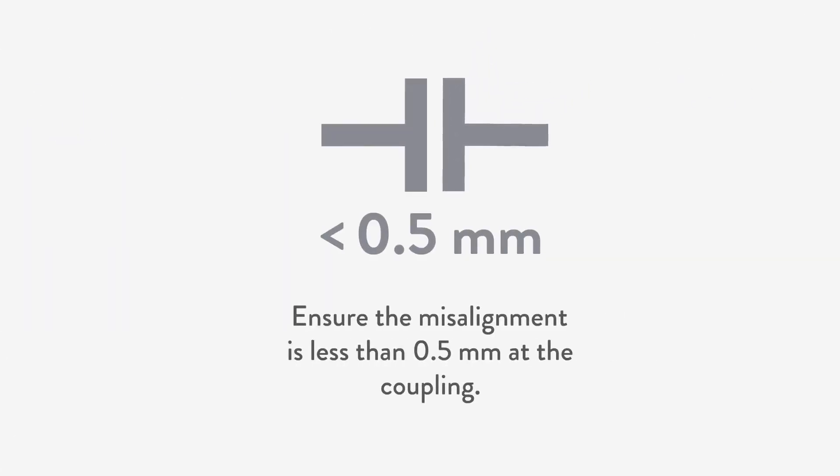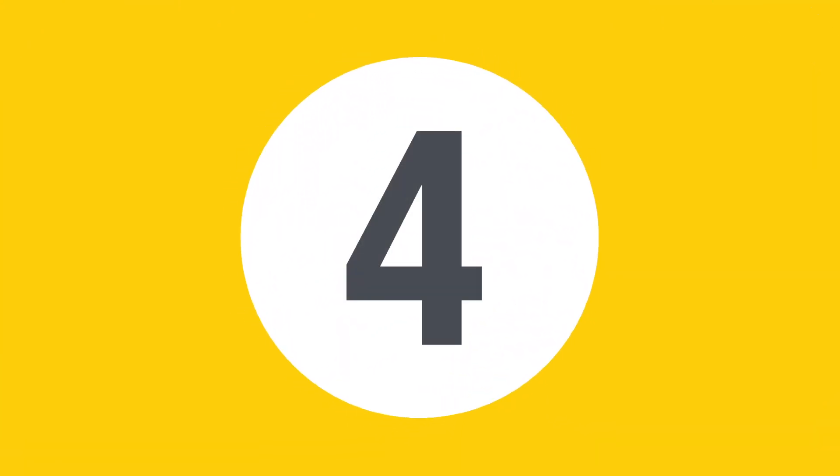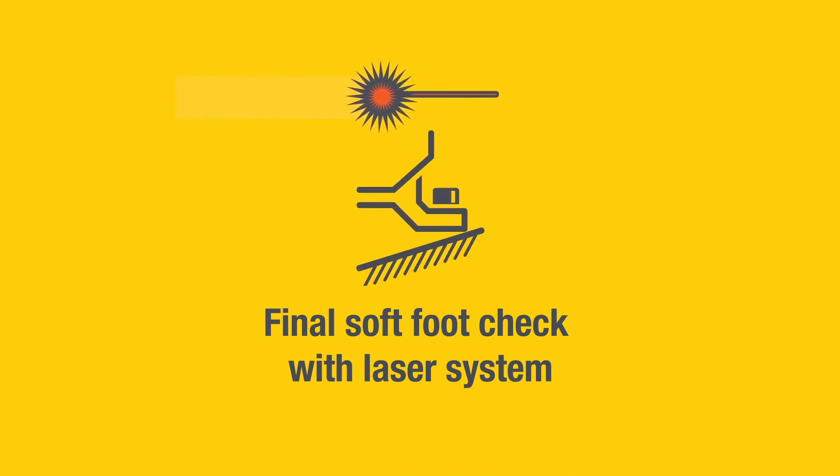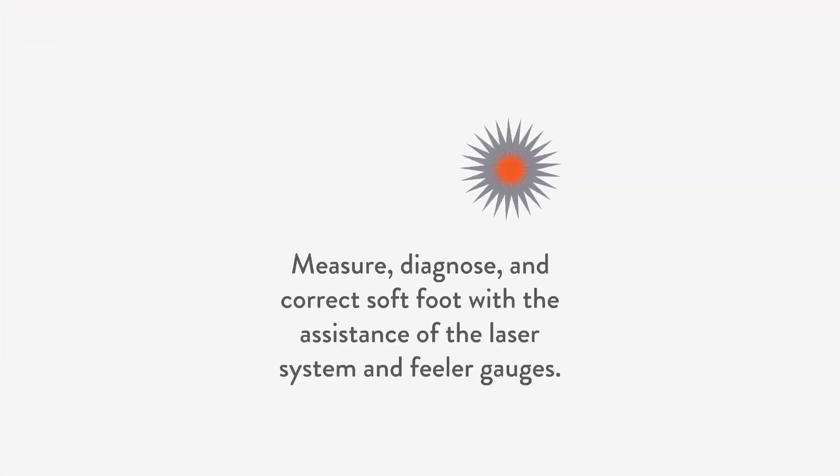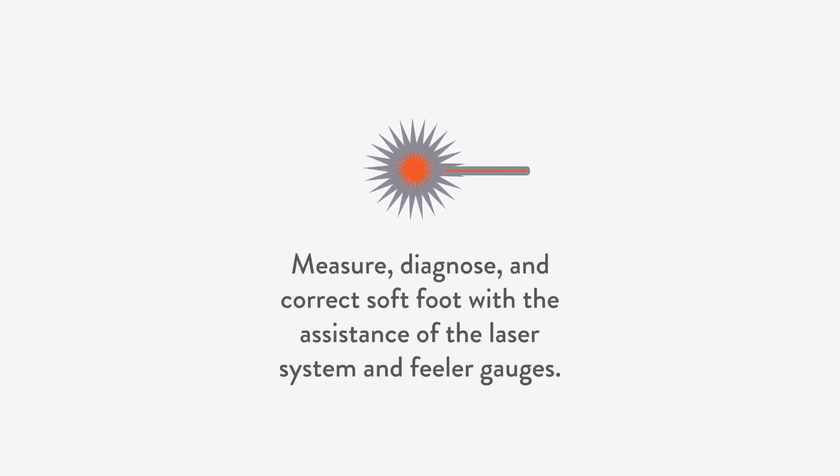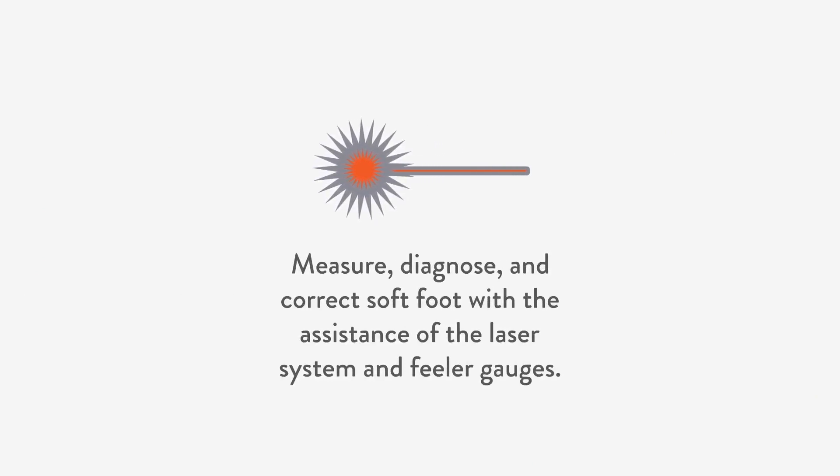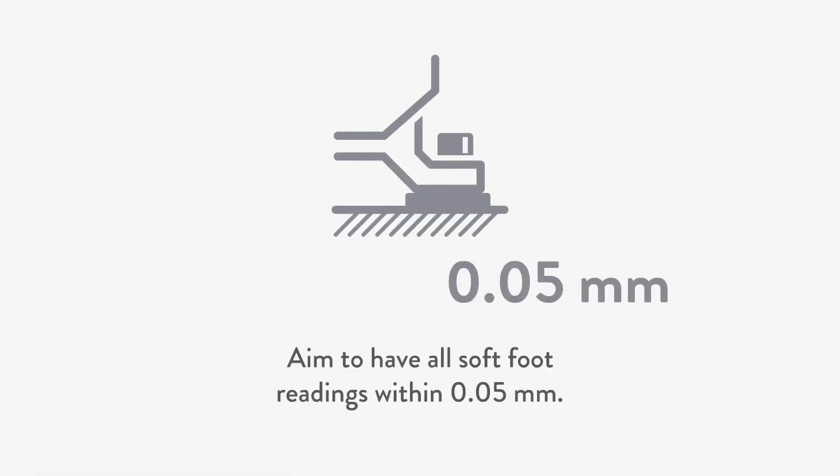In the fourth step, we diagnose and correct soft foot. Do this with the assistance of the laser system and feeler gauges. Aim to have all soft foot readings within 0.05 millimeter.